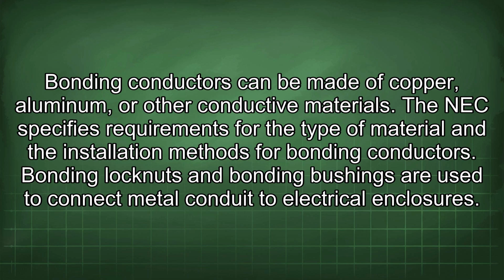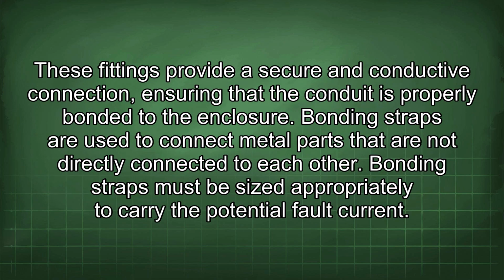Bonding locknuts and bonding bushings are used to connect metal conduit to electrical enclosures. These fittings provide a secure and conductive connection, ensuring that the conduit is properly bonded to the enclosure. Bonding straps are used to connect metal parts that are not directly connected to each other. Bonding straps must be sized appropriately to carry the potential fault current.